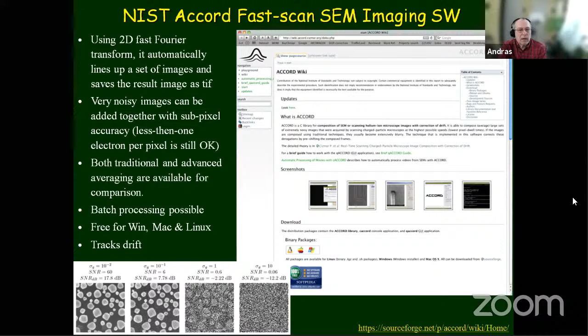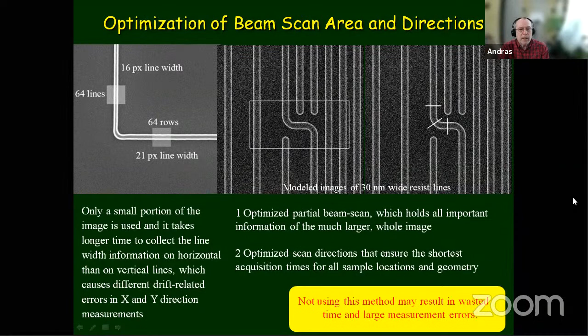So then, okay, we have an instrument which is not contaminating, and all kinds of good things are already being done to it. What can we do otherwise? One thing for sure is do not acquire information that you either already know or are not interested in. For example, if you want to measure the width of the line in the vertical and horizontal direction, there is no point acquiring the whole image, throwing away a lot of data and using just what you want. Choose only the area where the information you are looking for is, and better yet, acquire information the fastest way. So obviously, this means that we have to do better than the traditional scanning method. Next slide, please.